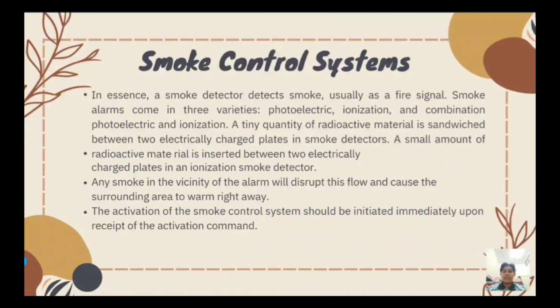Smoke control system. In essence, a smoke detector detects smoke, usually as a fire signal. Smoke alarms come in three varieties: photoelectric, ionization, and combination photoelectric and ionization. A tiny quantity of radioactive material is sandwiched between two electrically charged plates in an ionization smoke detector, and any smoke in the vicinity of the alarm will disrupt this flow and cause the alarm to trigger right away. And last, the activation of the smoke control system should be initiated immediately upon receipt of the activation command.